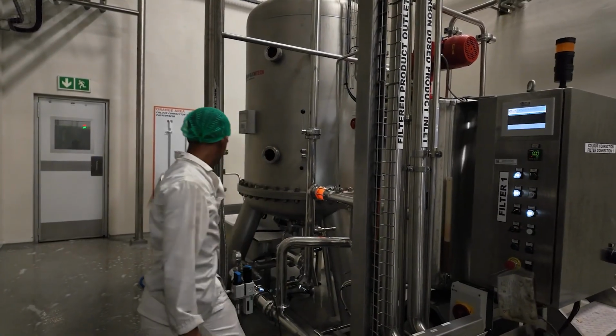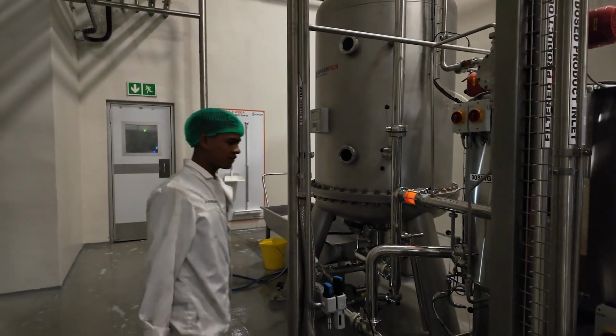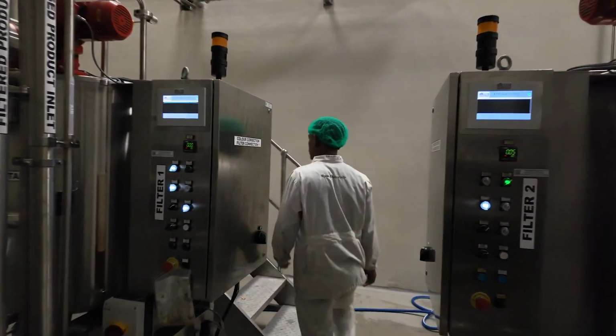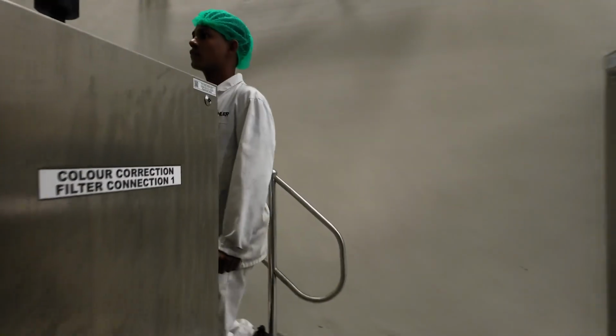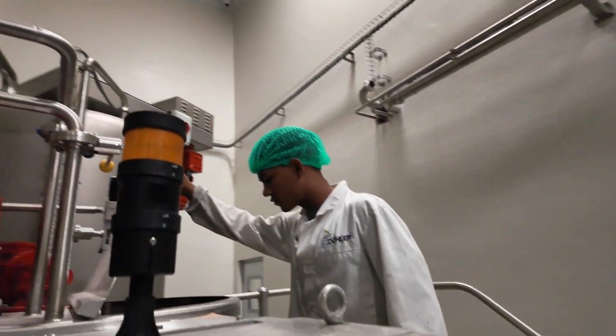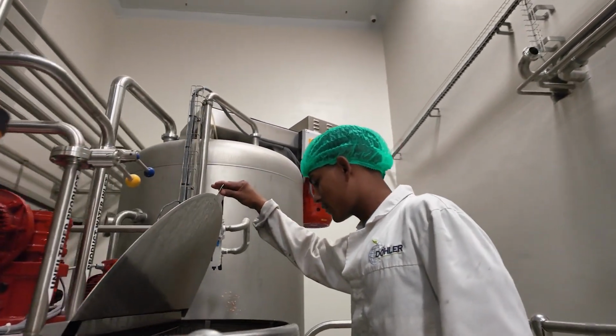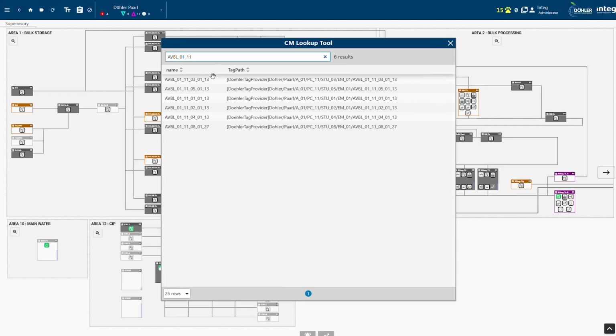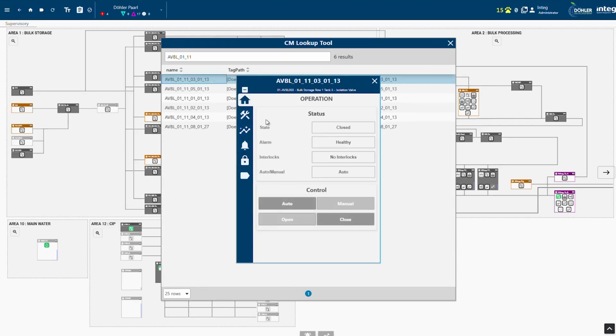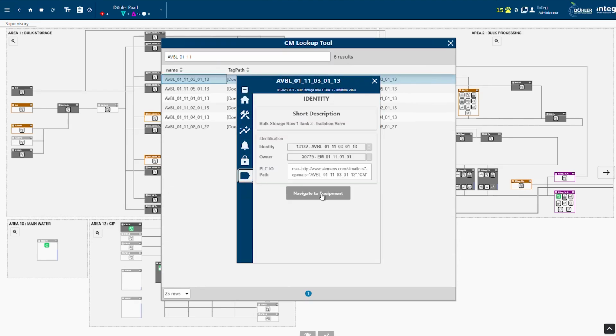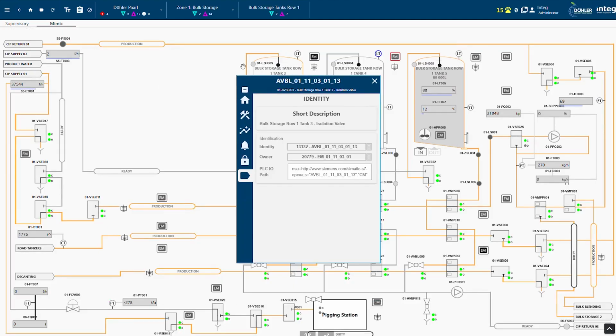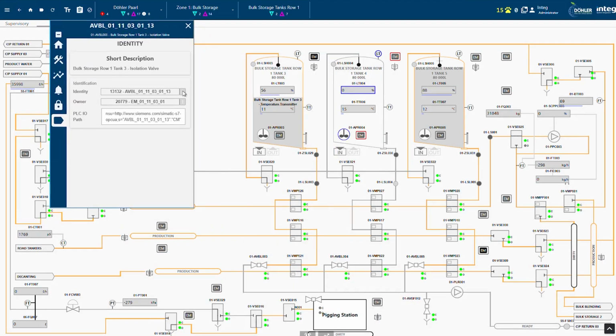Because of the size of the plant, it's difficult to know exactly where each valve or instrument is. If a fault occurs, it's easy to see on the HMI, but physically finding it in the field is difficult. So we developed several features, including a search function that takes operators to that specific item so they can find the faulty instrument in the field.